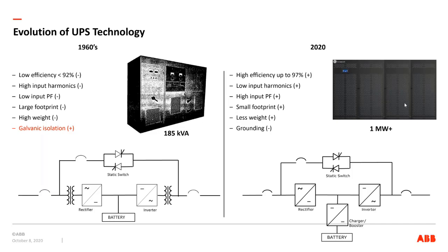The most modern UPSs can operate in that mode, and can even operate in that mode if there's a ground fault on the battery. So it requires that special application with high resistance grounding, but we are back to where, in that case, the UPSs can handle a ground fault on the DC side as well. So that was a little bit around the UPS.